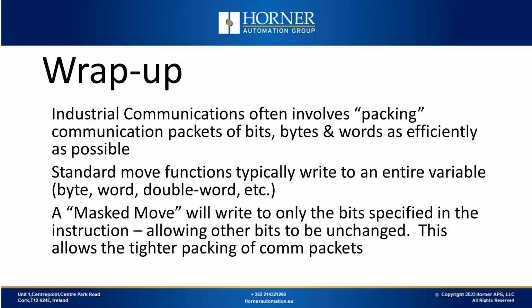In industrial communications, efficient packing of communication packets, whether for cellular, satellite, or lighting sequencing, is crucial. Standard move functions and bitwise operations often write the entire variable, be it a byte, word, or double word, potentially overwriting unintended data. However, a masked move instruction selectively writes to specified bits while leaving the rest unchanged. This ensures precise data manipulation without the risk of inadvertently altering important information.